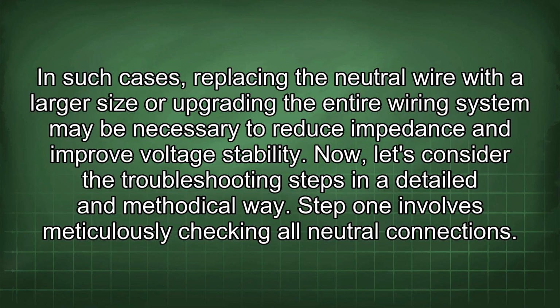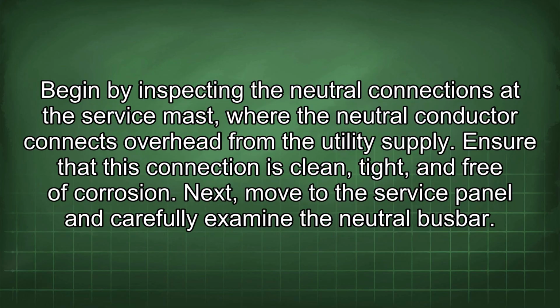Now, let's consider the troubleshooting steps in a detailed and methodical way. Step 1 involves meticulously checking all neutral connections. Begin by inspecting the neutral connections at the service mast, where the neutral conductor connects overhead from the utility supply. Ensure that this connection is clean, tight, and free of corrosion.